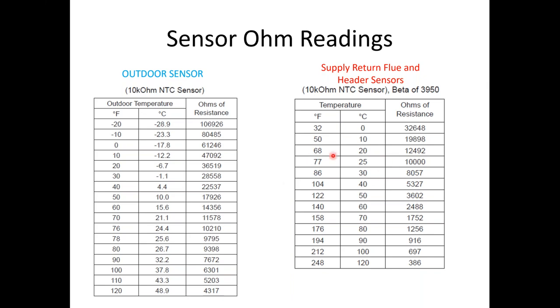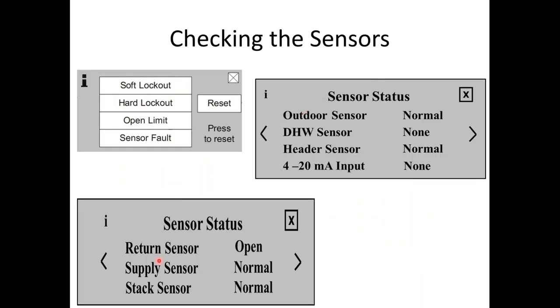In some cases, with the supply sensor, you'll get, on the screen here, it'll say unreliable. That's usually, it's out of range. It is a defective supply sensor, but that error will sometimes drive you nuts because it will come and go. And when that shows up, it's usually around the 150 to 170 degree range.